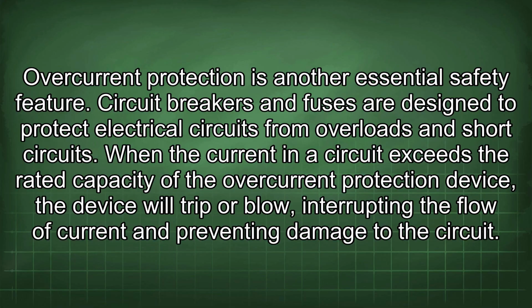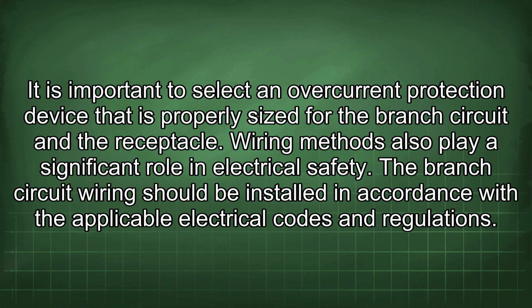Overcurrent protection is another essential safety feature. Circuit breakers and fuses are designed to protect electrical circuits from overloads and short circuits. When the current in a circuit exceeds the rated capacity of the overcurrent protection device, the device will trip or blow, interrupting the flow of current and preventing damage to the circuit. It is important to select an overcurrent protection device that is properly sized for the branch circuit and the receptacle.